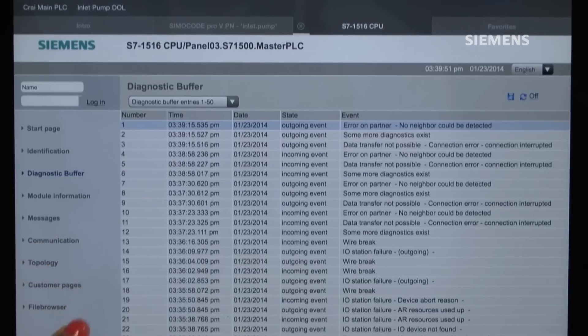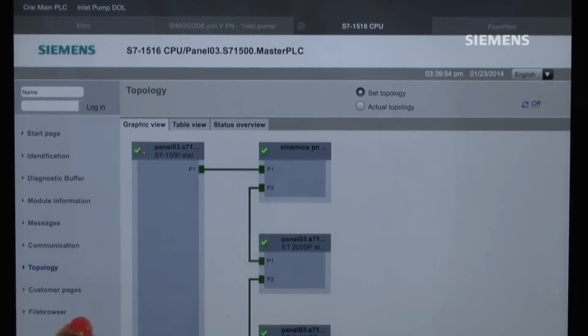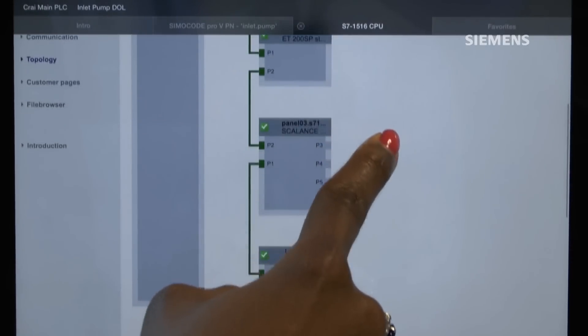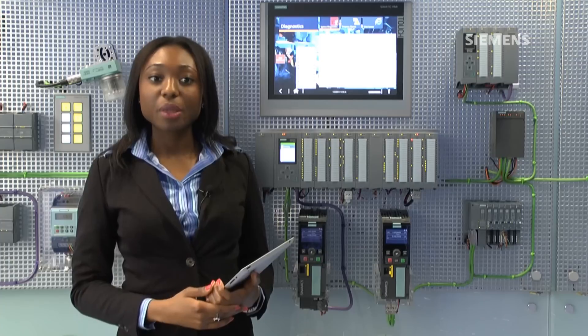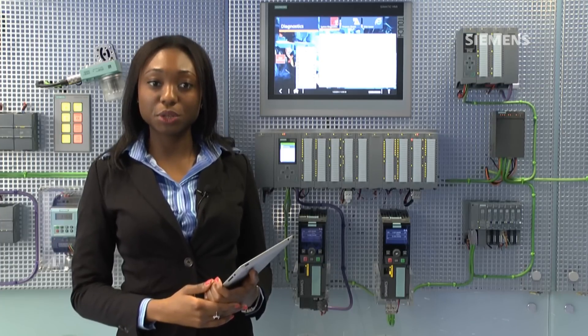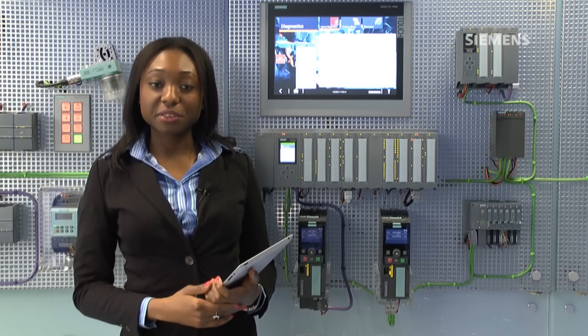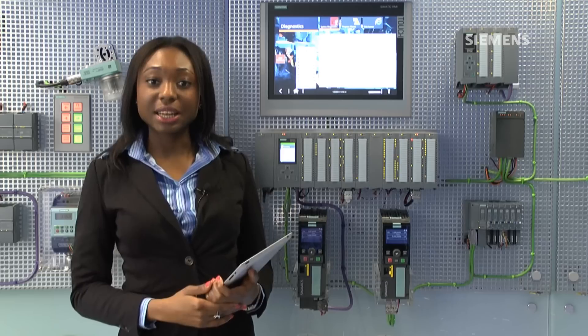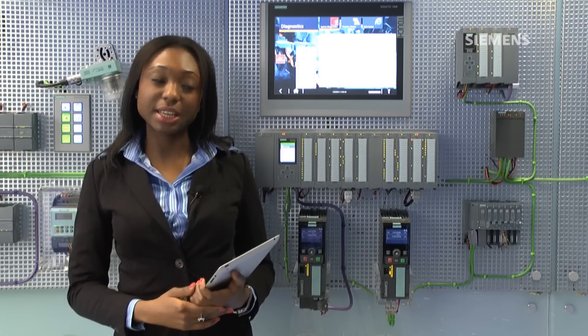Under topology, the PROFINET network architecture is displayed and can be used to diagnose faults. We can see media redundancy protocol is being used, and all the PROFINET devices are connected in a ring. As an example, if the ring is broken by removing a cable, then this is highlighted in yellow.